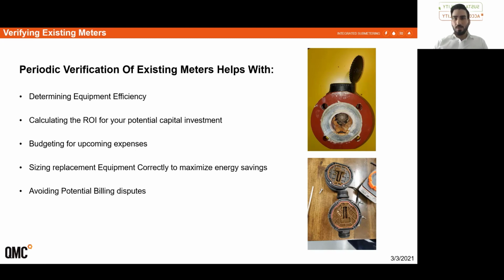The top meter, as you see, is a domestic hot water meter that has been in service for less than 5 years. In the first place, it's worrisome because this is on the domestic hot water system, so it's the drinking water, and it raises questions about the water treatment system within the facility. But also, this is a meter that is being used to track consumption for billing purposes as well. So we were called into the property because the cold water feed into the domestic hot water system, along with the hot water outlet and the recirculation water, were not adding up. So we went to the property with a set of clamp-on meters to verify the performance of these water meters, and sure enough, there was a huge discrepancy between the measured value of the clamp-on meters that were installed out in the field temporarily and the permanent meters.